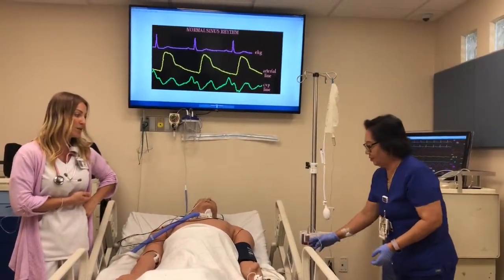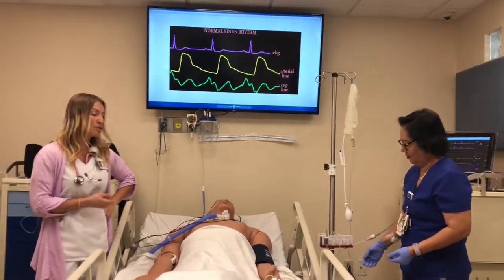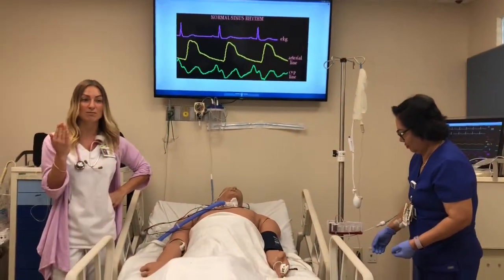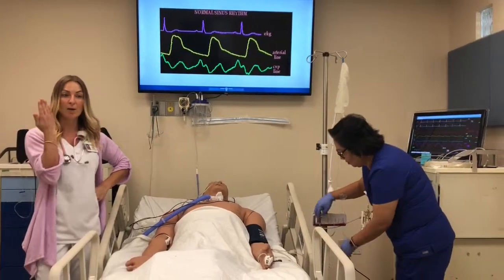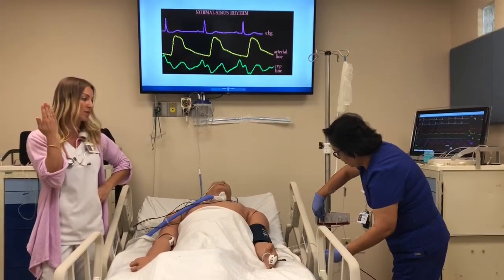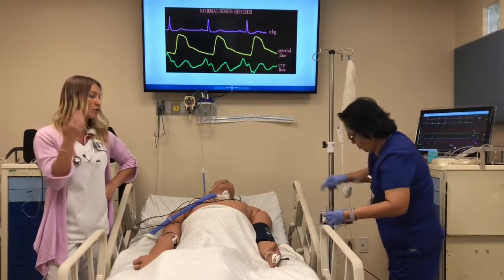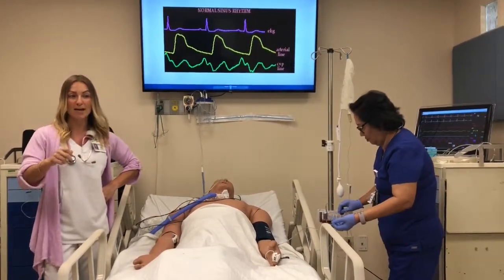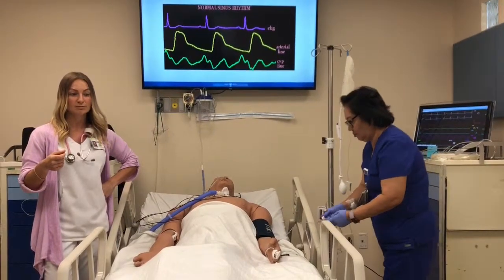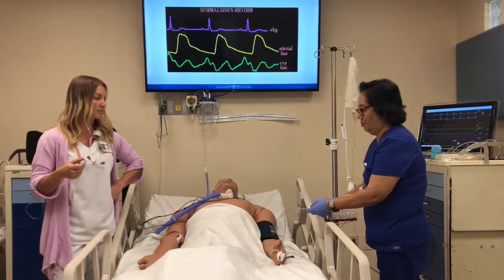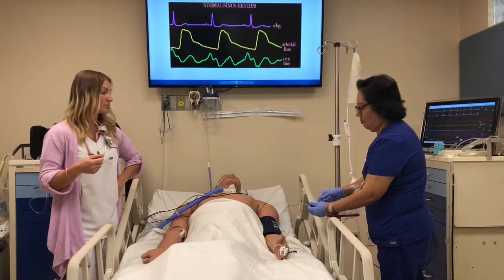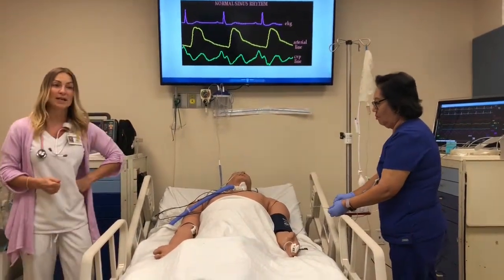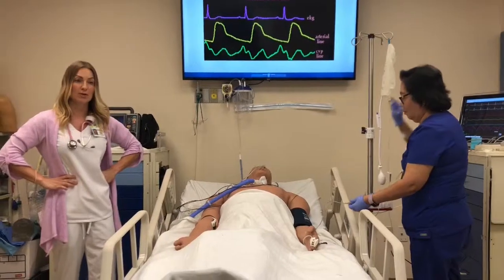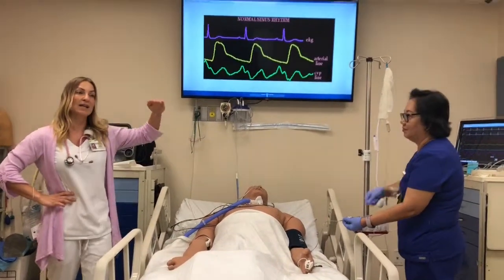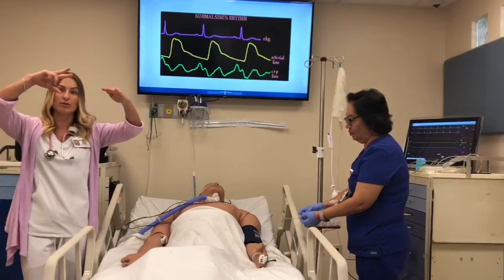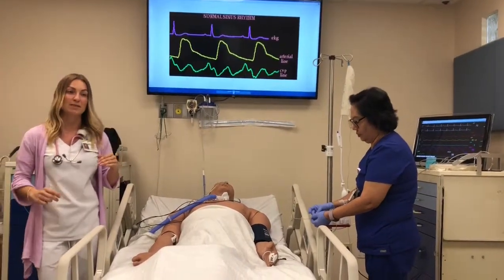After we have done that, you're going to shut off the system to the patient, meaning you're going to turn the stopcock up to the top, which means off to the patient. You're going to open up the white or blue cap open to air. And you're going to want to press 0 on the monitor. This should zero it. Wait until that line becomes completely flat and it's going to show 0 over 0. That means it's properly been zeroed.